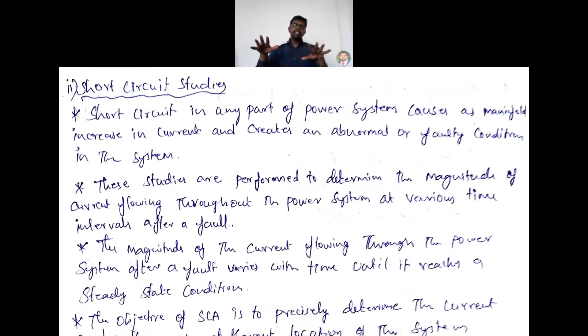These studies are performed to determine the magnitude of the current flowing throughout the power system at various time intervals after the fault. To study this, they simulate the model and inject an artificial fault, injecting more current into that particular line, then observe what happens to the system, whether the circuit breaker trips or not, and check everything like that.